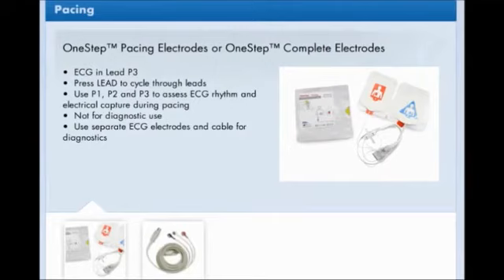For one-step pacing, the ECG signal appears in lead P3. Press the lead button to cycle through the leads, P1, P2, and P3, to choose a lead with good visualization and proper sensing of the R wave. P1, P2, and P3 are non-standard ECG monitoring lead vectors used for one-step pacing. The ECG display may be slightly different than with standard leads.